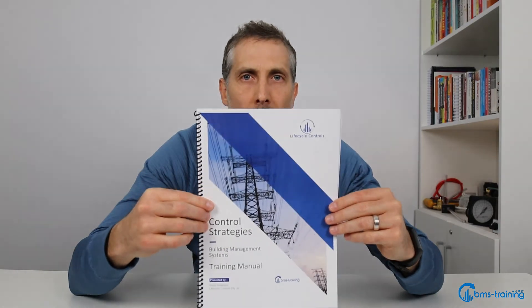This control strategy is always implemented, and even in my own BMS specification I have the same control strategy — describing how, as the building's load decreases, you raise the temperature to make the chillers more efficient. But in the control strategy course manual where we actually describe and talk about this, there's a section that says: be careful. If you're going to do this, you have to consider the knock-on effect.